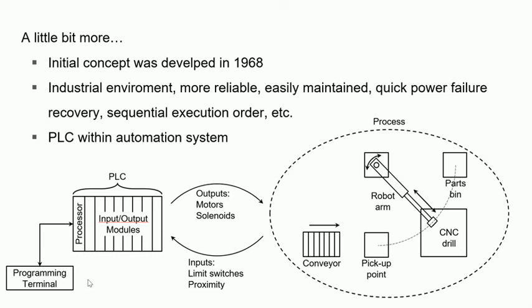A little more information: the initial concept of PLC was developed in 1968, which is a really long time ago. However, it is still widely used in industry because of several reasons. First, it is really reliable in the industrial environment and very easy to maintain, especially compared to personal computers. It also has a really quick power failure recovery — a PC takes roughly five to eight seconds to restart, whereas a PLC normally only takes one to three seconds. Another advantage is that it executes everything in a sequential order.